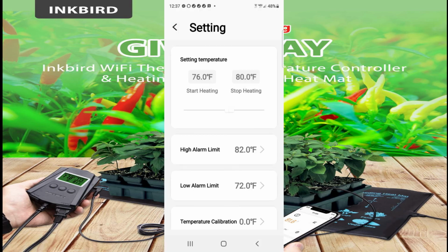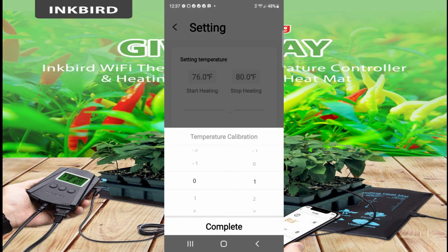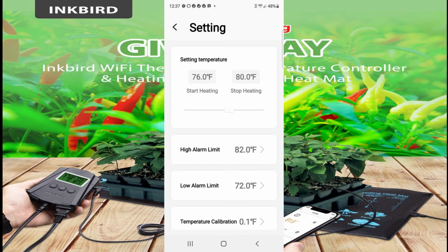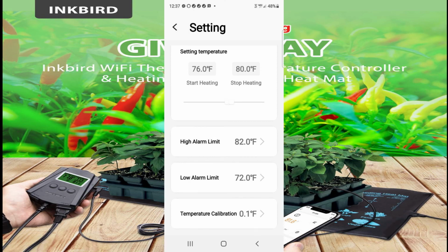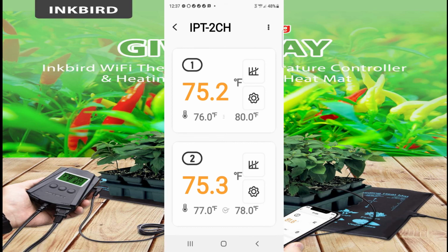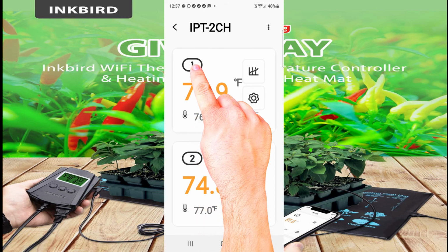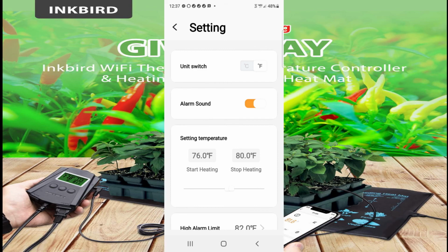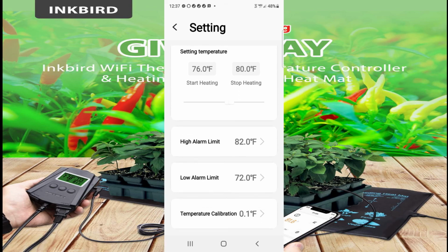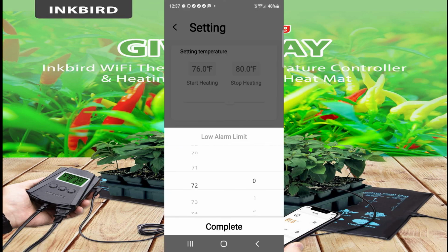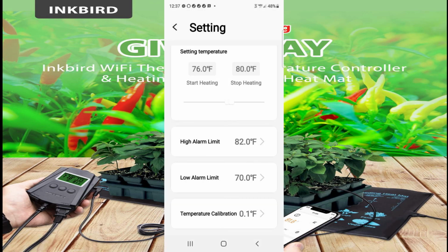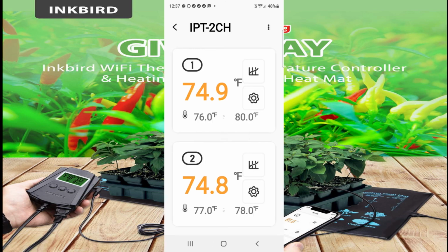Now the temperature calibration, I'm going to open it up and let's just say we'll set it to 0.1, so 1/10 of a degree off on calibration. And that one's done, and then I go to 1. I'm going to open that one up. And now I'm going to go through the same settings, verify that everything's the same or where I want it to be. Let's say I want to make a change here to the low alarm and I set it for 70 degrees. And I'm complete here.